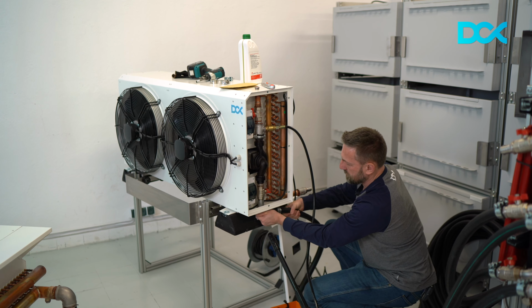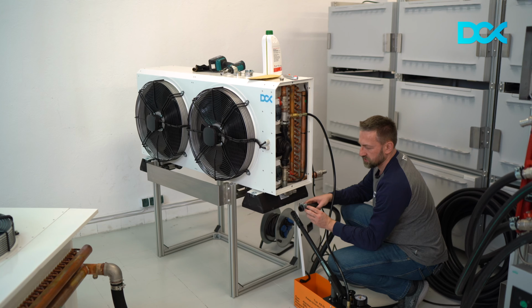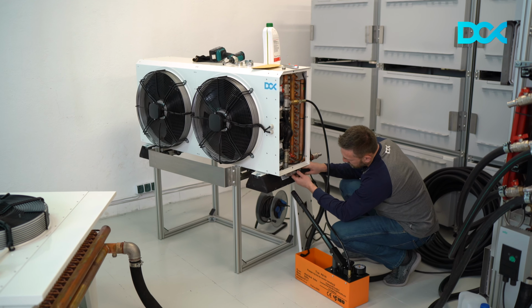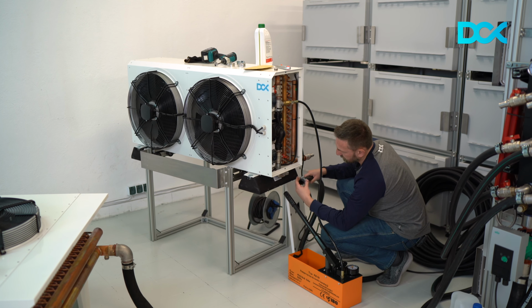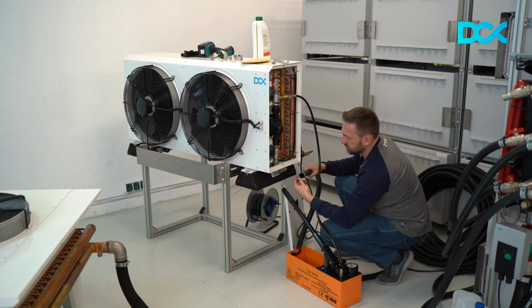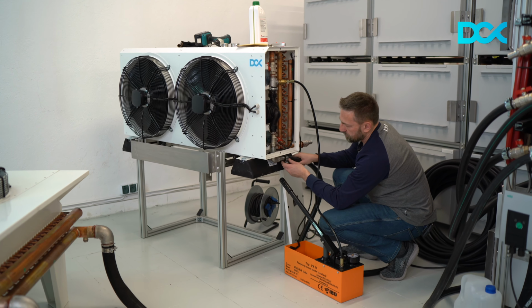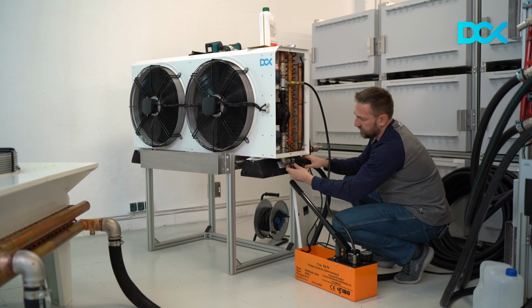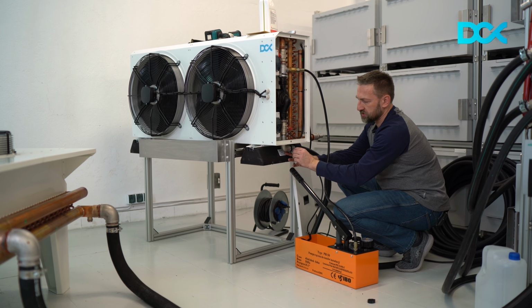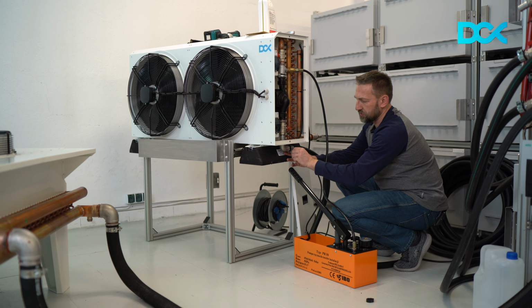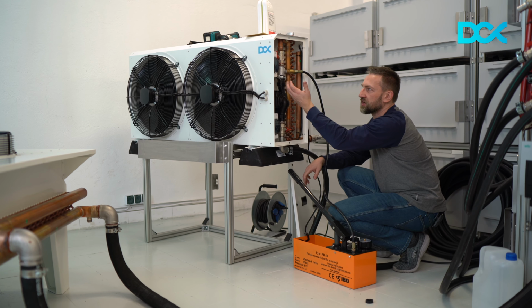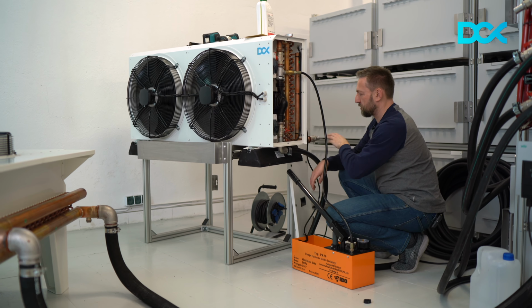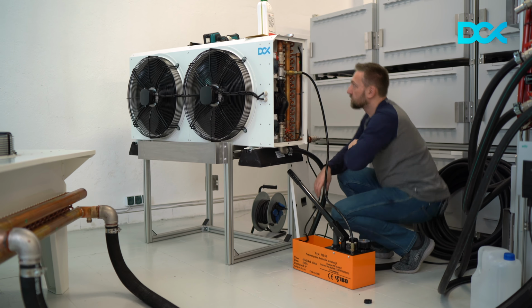What I'm going to do, and this is also important, I'll connect it like this, having that screw here on that side. It would be easier for me to connect everything, or I can do that on the bottom. These are some small things, but you need to remember that position is best - basically the connection on the bottom. This is the inlet for the enclosure, where the pump sucks all the water through, goes through the dry cooler, and comes back through that fitting. So let's take the rest of the hose.